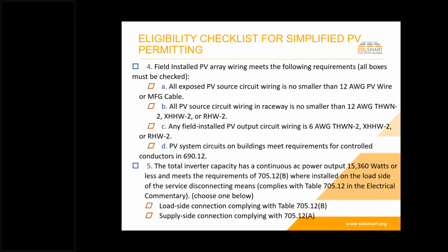All PV source circuit wiring in raceway is no smaller than 12 gauge THWN-2 or XHHW-2 or RHW-2, and those products are also very readily available, but all our calculations are based on these types of wires for ampacity and conduit fill and all the things that you have to worry about on the electrical side.